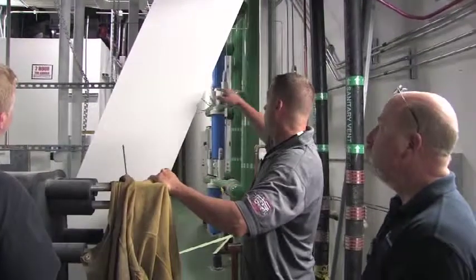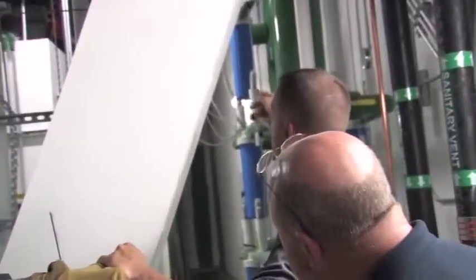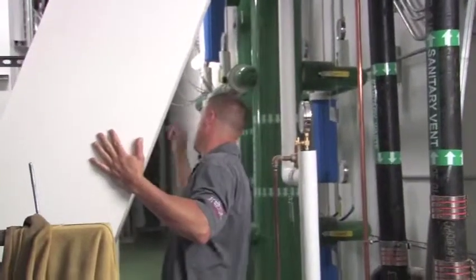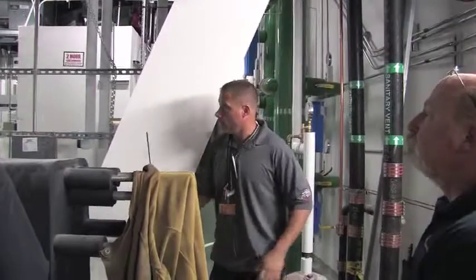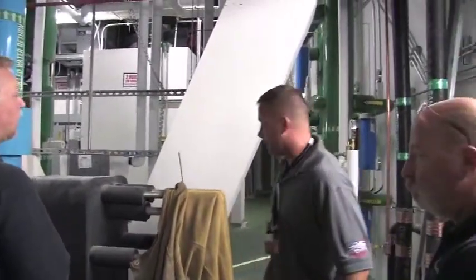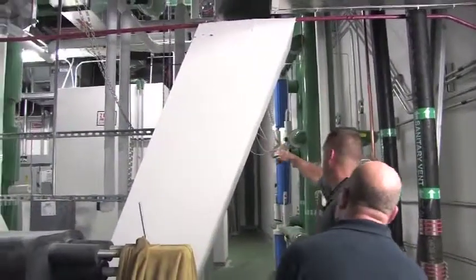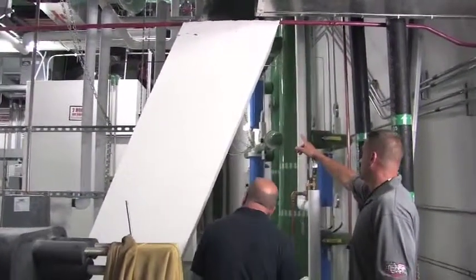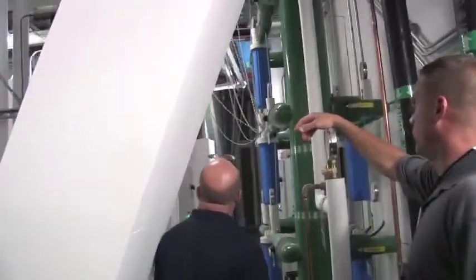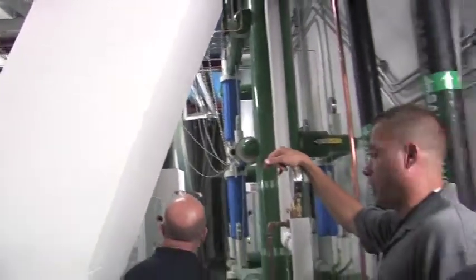The two hot waters come out of the shaft right behind the elevator. They're right up on top of the chill water lines. Then they run over behind the electrical room and go down the shaft. I'll show you over here where they head down. Now right here's your DP. Right up here, if you look above that roof, that's your DP valve and the sensors, the 2-inch gray. That's where the hot water DP is.